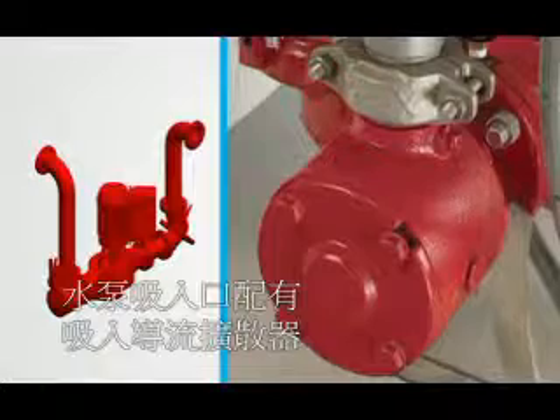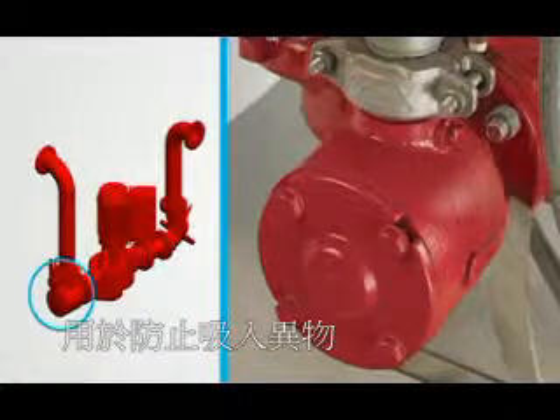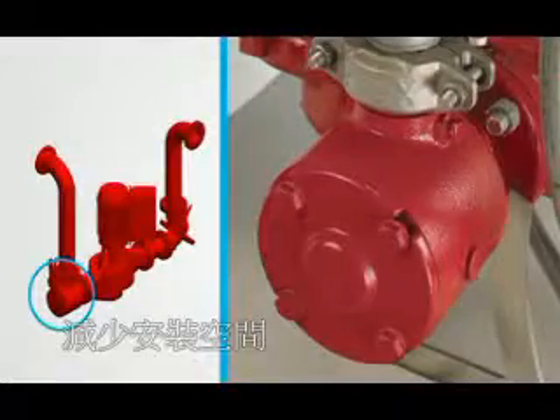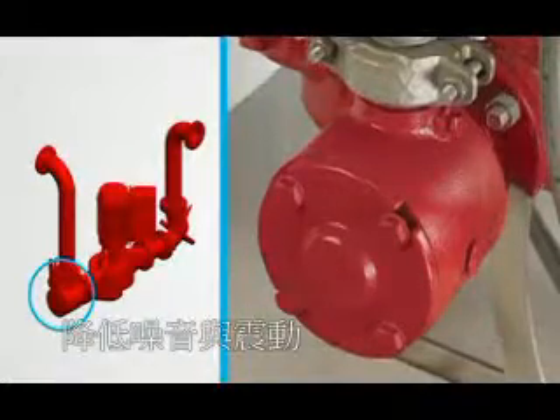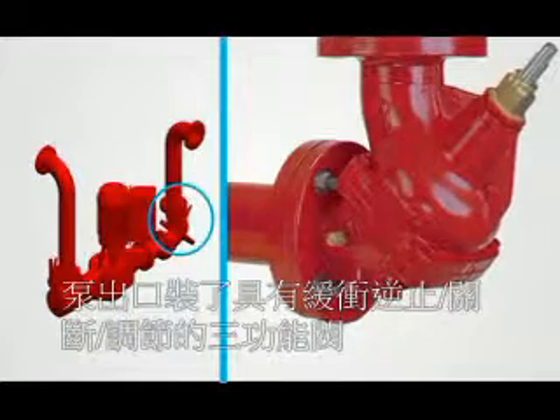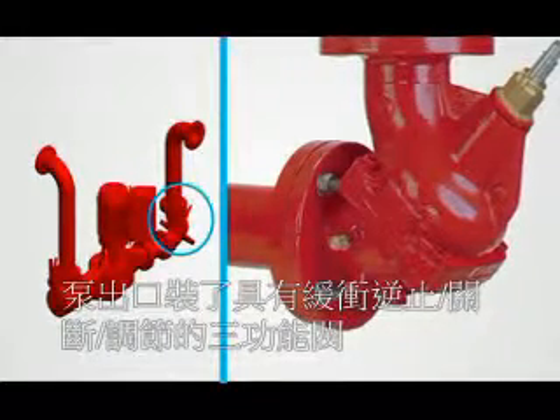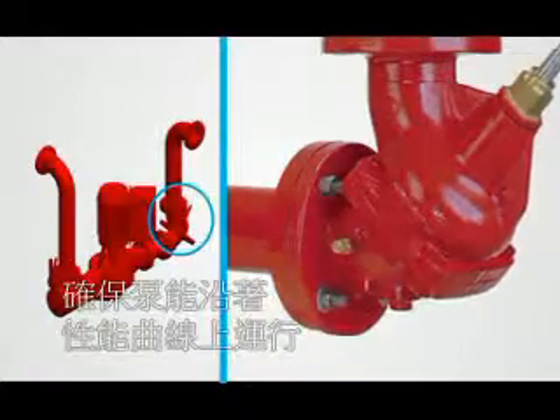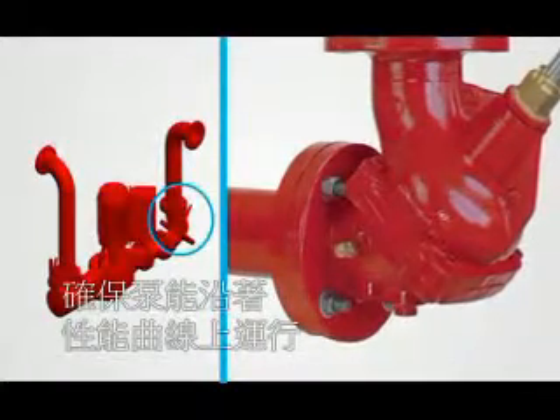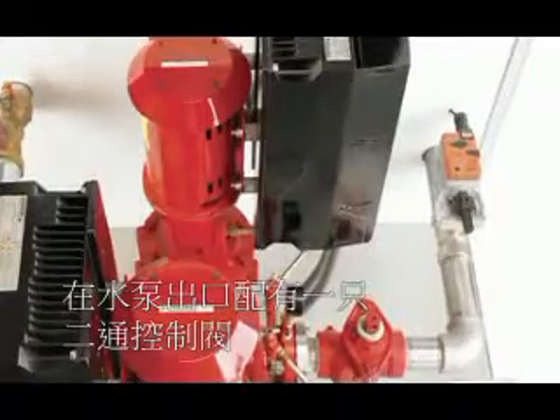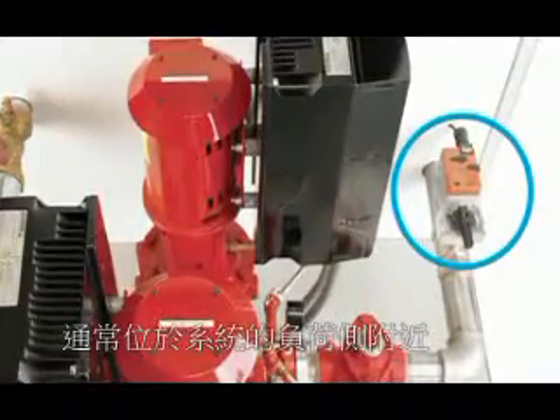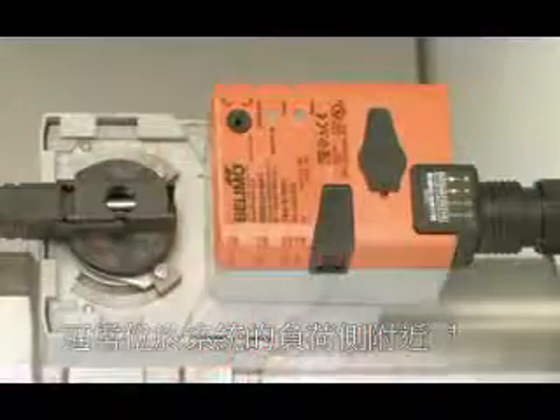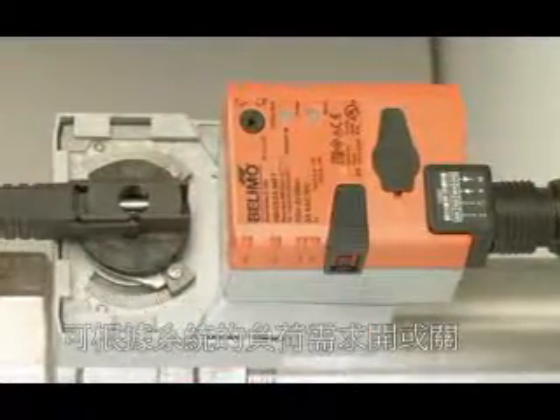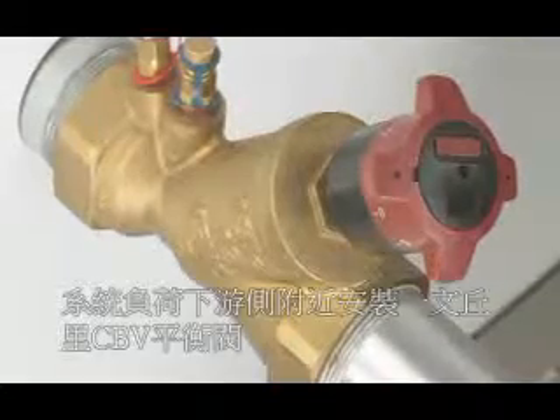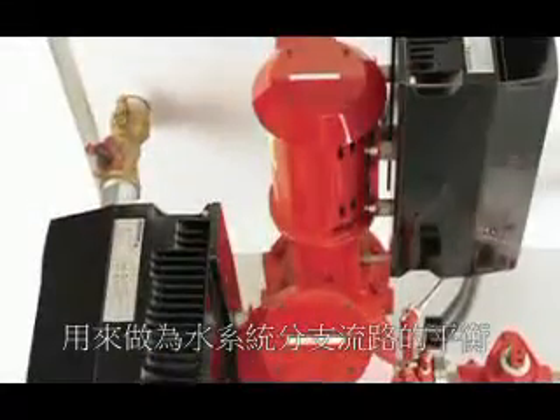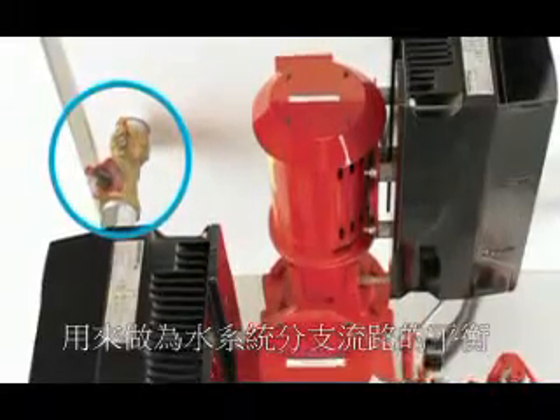It is equipped with a suction guide located at the pump suction to prevent debris from entering the pump and minimize turbulence that could cause unwanted noise and vibration. A 2-inch triple function valve on the pump discharge offers a check feature, isolation feature, and throttling capability to keep the pump on its curve during operation. Downstream of the pump discharge, we have a two-way control valve that would be typically located near a load in the system, opening and closing depending on system load requirements. A 2-inch Venturi-style CBV balancing valve is typically installed downstream of the load to balance the branch.